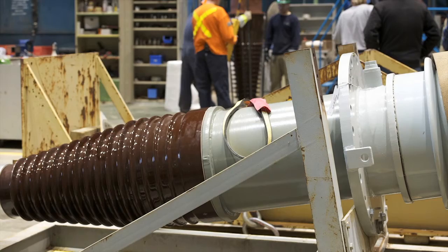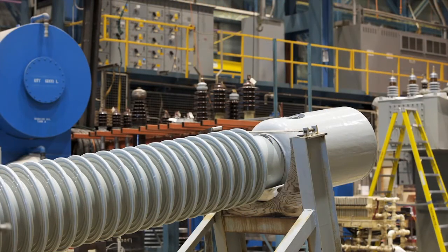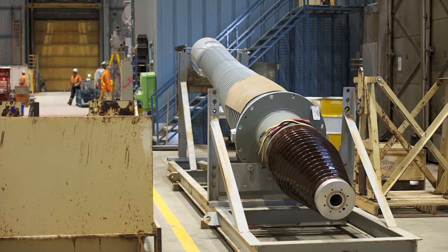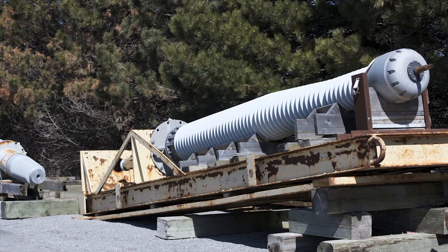As electrical networks became more sophisticated, the need was recognized for a means to better distribute the electric field generated across a bushing, especially at the higher voltages. This resulted in the development of designs that were capacitance graded, or as the IEC definition for such condenser bushing states, in which the desired voltage grading is obtained by an arrangement of conducting materials or semiconducting layers incorporated into the insulating material. The basic principle was to try to distribute and equalize the natural electric field between the conductor and the earthed flange. This would be accomplished by employing intermediate conductive layers radially, in other words, to lower the field at the conductor so as to better utilize the insulating material, and axially, that is, near the flange, to allow for higher flashover voltages for any given arcing distance.